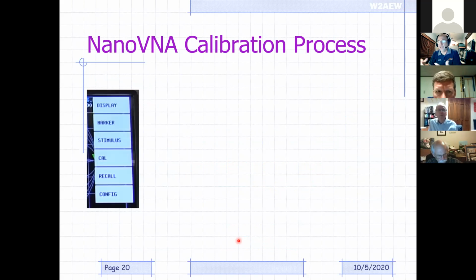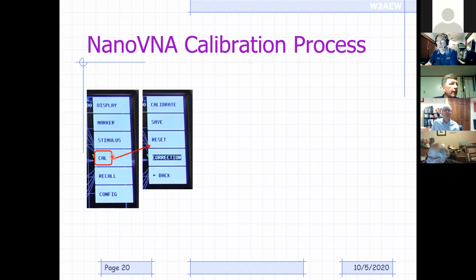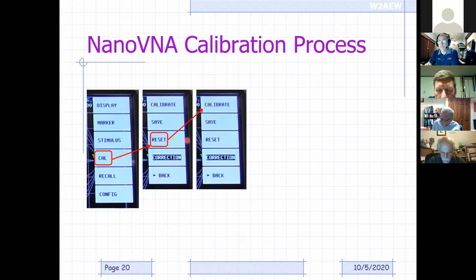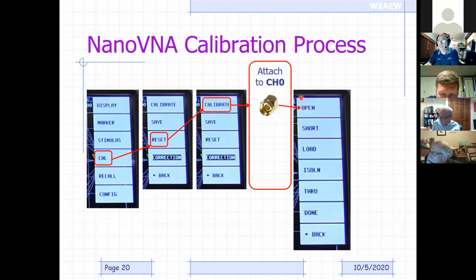And again, this will just run you through to kind of show you the menu steps. So this is the root menu, or the bottom menu, or the main menu for the VNA. So you hit cal, that brings up the calibrate menu, and then you hit reset. Reset basically resets the existing calibration standards or calibration corrections that are loaded. And then once you hit reset, you hit calibrate, and then calibrate will bring up this menu over here.